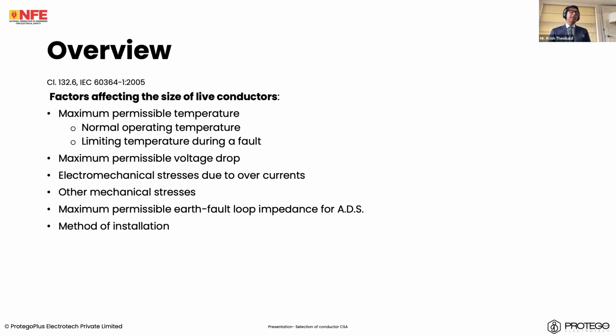Any electromechanical stresses that can occur due to overcurrents, especially short circuits, in your single core cables can move around quite a bit. Any other mechanical stresses the insulation is subject to? Most of our installations are protected by the measure of automatic disconnection of supply, and there the earth fault loop impedance value is very important. We've been talking about testing earth fault loop impedance quite a bit, but it is also very important that the installation is designed keeping in mind these earth fault loop impedance values. And of course, the method of installation is also relevant.